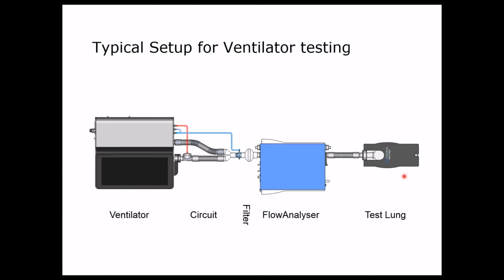This is a typical setup we have for the PF300. We have a ventilator or anesthesia machine with its conventional setup, with its conventional circuit. Then we have a filter, and we have the PF300, which measures everything which is delivered to the test lung or coming back from the test lung. This is a quite typical setup for ventilator testing, which is usually used for annual maintenance.